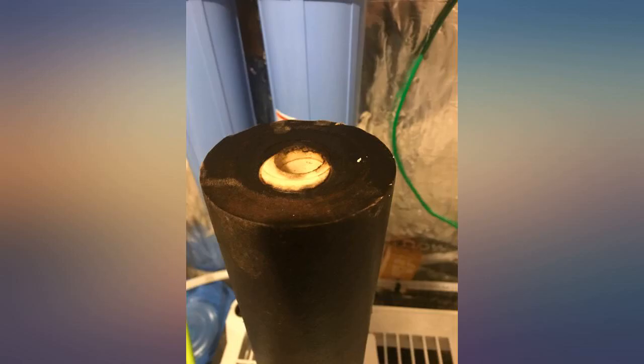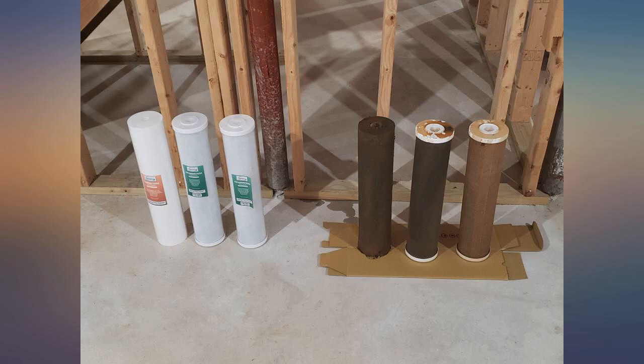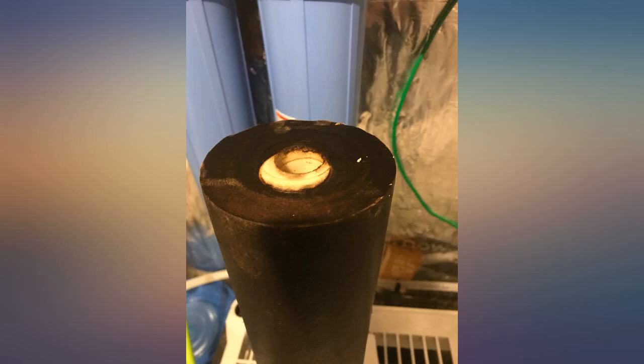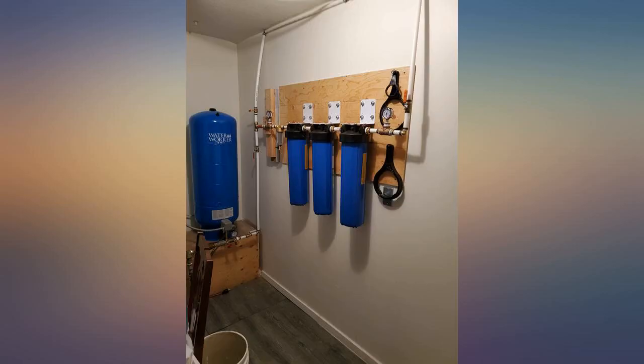They filtered just fine, but they are not easy to install — not the fault of the manufacturer, but a fact of purpose and use. The filter containers are full of water unless you have a drain valve, and they take forever to drain through a small hole. The filters inside are equally full of water and the impurities that were filtered out, so they are heavy. The O-ring can get disturbed while you're threading the housing.